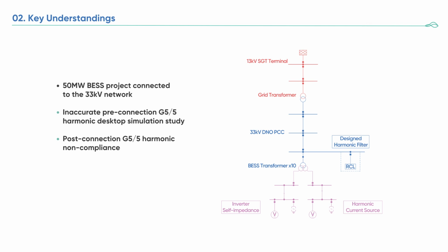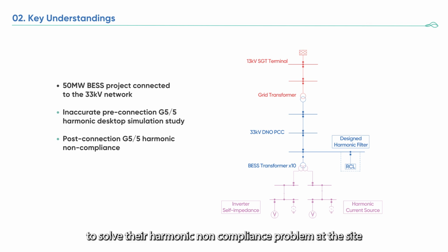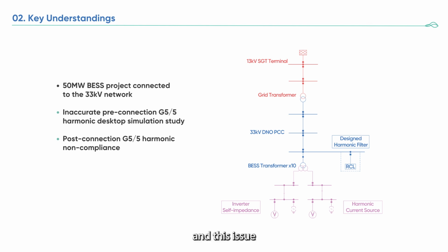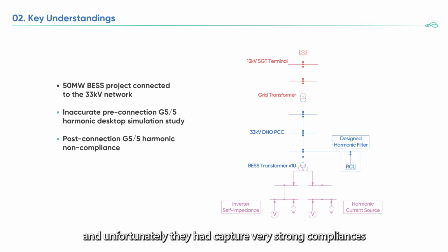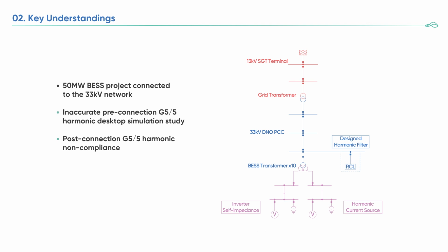Firstly, a client came to us to solve their harmonic non-compliance problem at the site. And this issue was not captured during pre-connection harmonic desktop studies. Everything was fine, everything was green in the original study. And the site has been constructed, energized, and the DNO, distribution network operator, did actual site measurement at the site. Unfortunately, they captured various non-compliances, which are between the 14th and 20th order, and also the 55th and 65th harmonic orders, which are quite uncommon for most of the drives or for most of the typical loads.